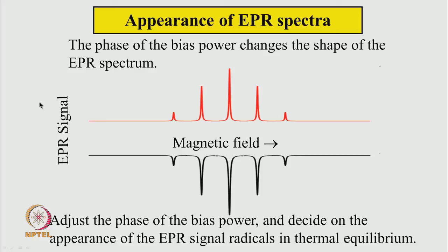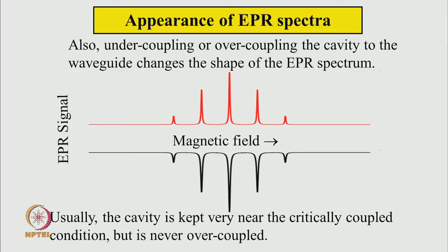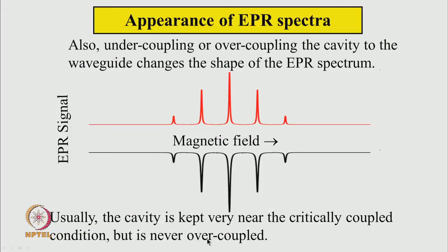We have to adjust the bias power and decide what sort of signal we want to record and display. We are often dealing with a signal from a radical which is in thermal equilibrium. In thermal equilibrium, the lower level has slightly more population than the higher level, so we get an absorptive signal. Whether a particular shape is called absorptive representation — that has to be decided once and for all. The appearance will depend on the phase of the bias power, but it will also depend on the cavity matching — under coupling or over coupling will also change the phase of the power coming out from the cavity. In practice, we never work in the over coupled condition; we work just a little bit less than the critical coupled condition.